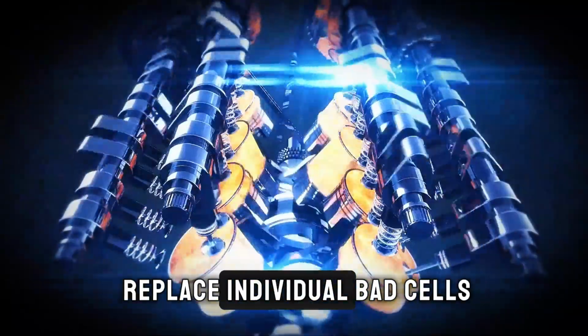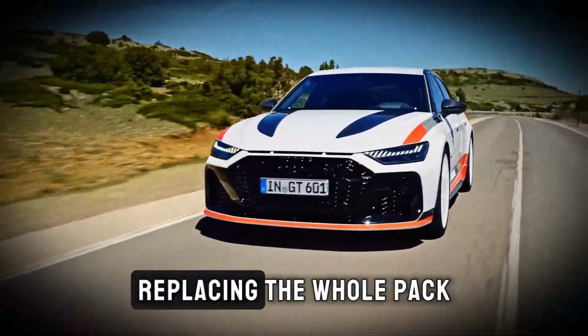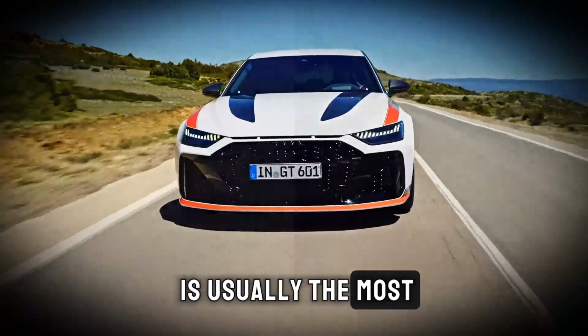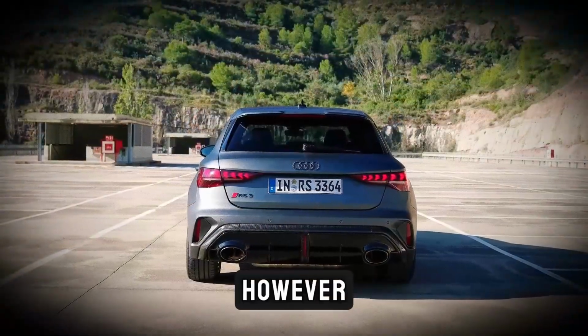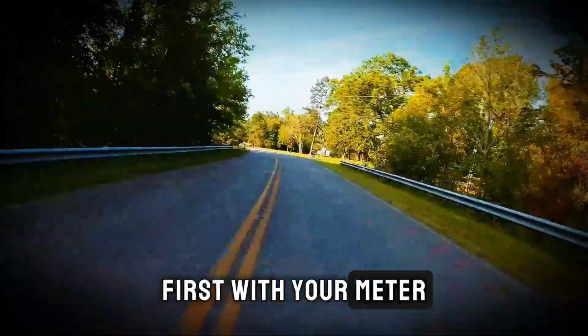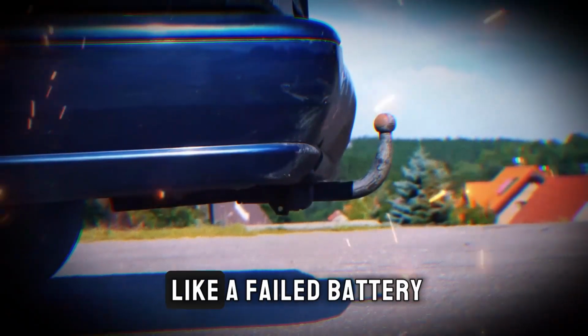While you can replace individual bad cells, honestly, replacing the whole pack is usually the most reliable long-term fix. However, always double-check the temperature sensors and voltage sensors first with your meter, because if a $5 sensor is lying to the computer, it can look just like a failed battery.